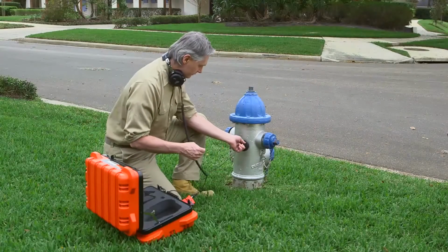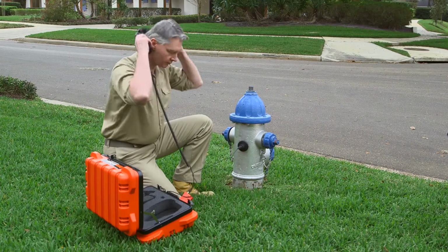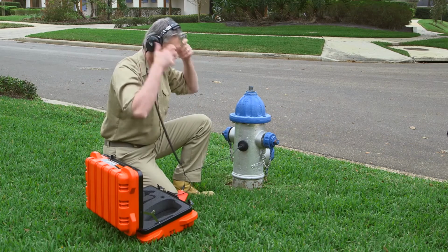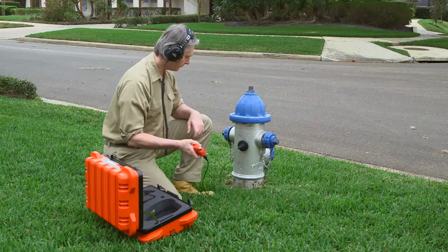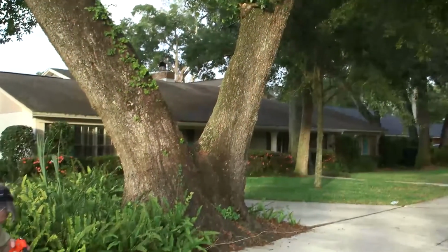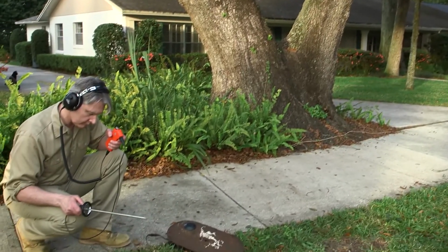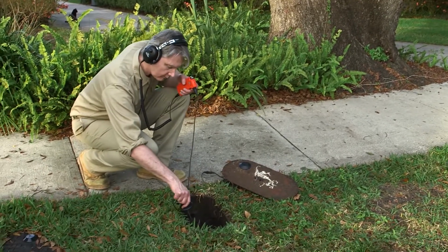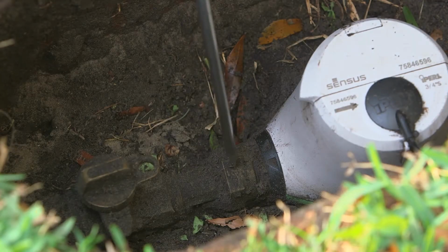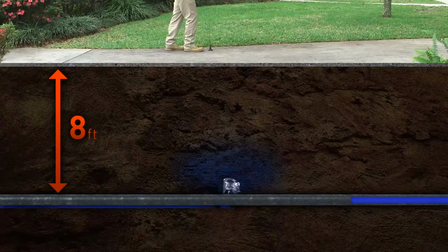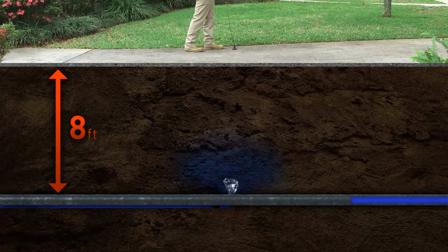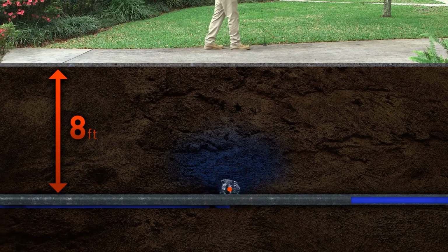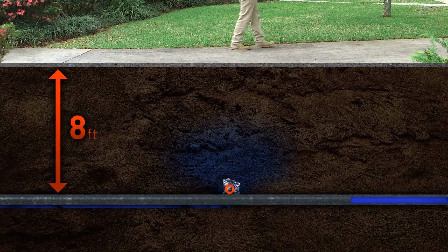The leak vibration travels down the length of the pipe. Leaks in metal pipes can be detected as much as 5 times farther away than in PVC pipe. Placing the probe directly on the pipe wall makes it easier to detect leaks at greater distances. And of course, the deeper the pipe, the harder it is to find the leak. To find leaks in lines buried deeper than 8 feet, increase the water pressure to amplify the sound.